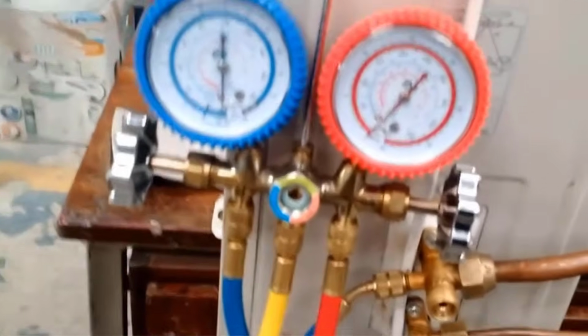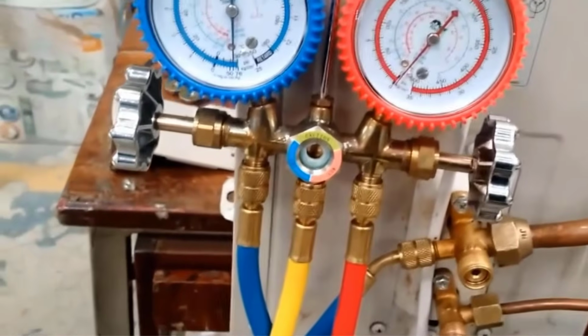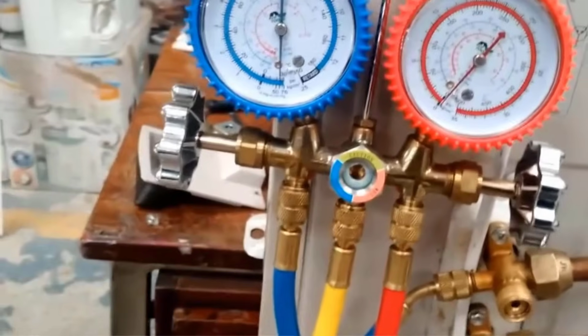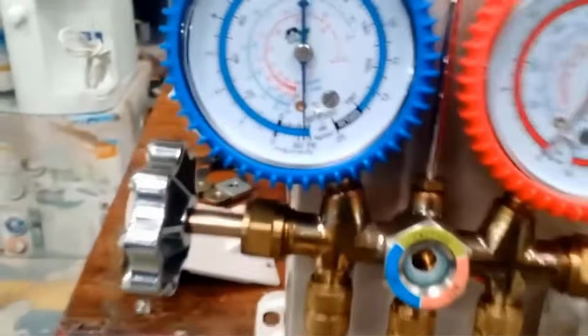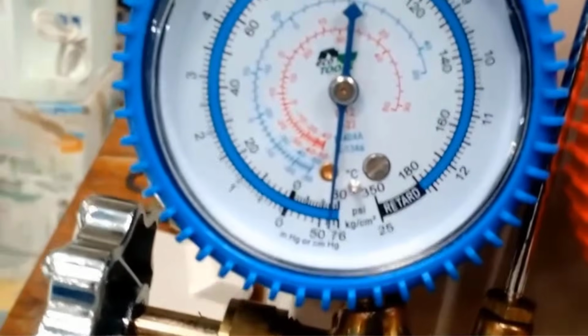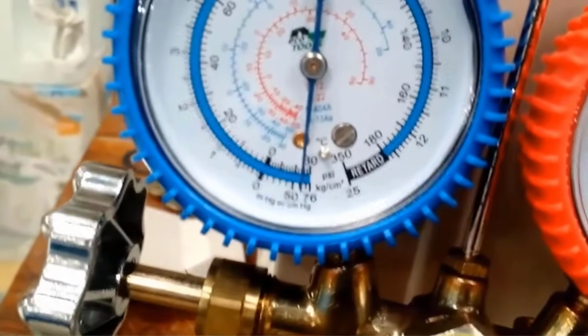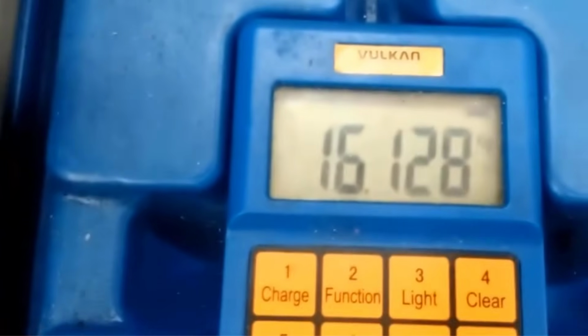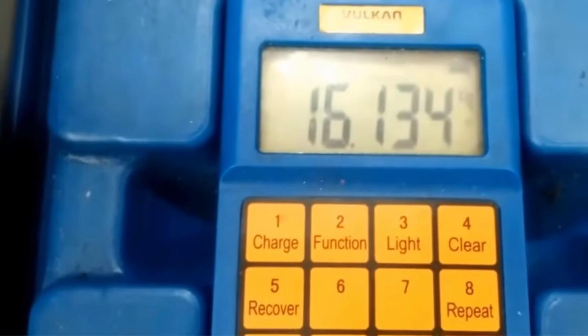Now, regarding the refrigerant leak, the technician needs to use a manifold to check the gas pressures, both high and low. Through these measurements, he can determine if there is a leak or if the amount of gas is correct. The manual lists the ideal pressures that should be found. If there is a leak, the pressure will drop constantly. This way, the technician can replace the gas and stop the leak, checking if any connections were not tightened correctly.